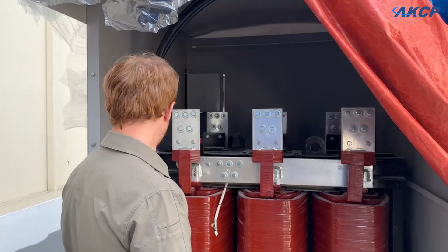You can see here how we're routing the cables inside of the transformer. They're pretty large cables, we cannot bend them on a tight radius, so that's why it's bending around here. These ones come down and terminate on one side, and we have another set that will terminate on the other side. We have to be careful how we route these cables because we want to make sure they don't touch the transformers, which can get hot during operation. We've also got an exhaust fan in this area that helps cool down the inside of the transformer casing, so we want to make sure no wires hit that and potentially get damaged.